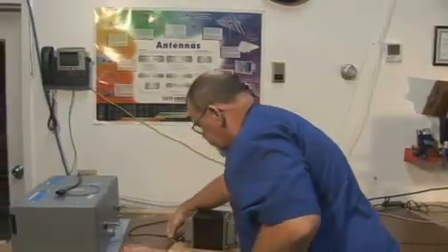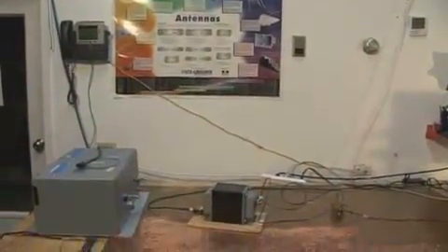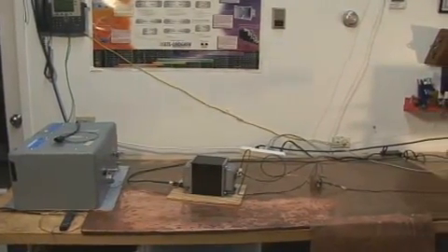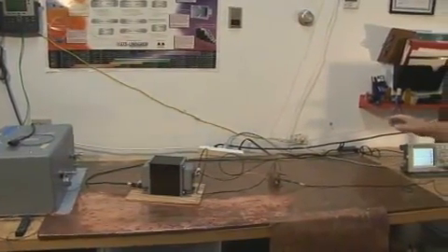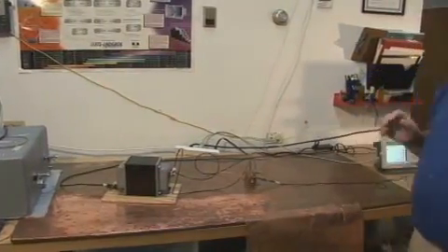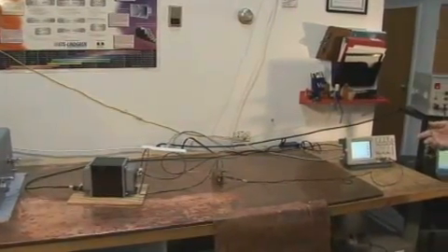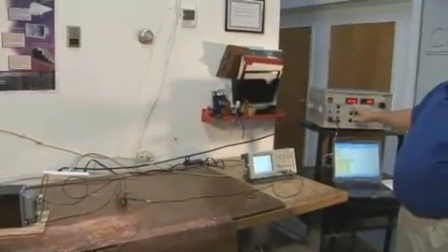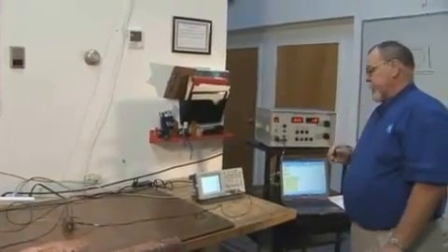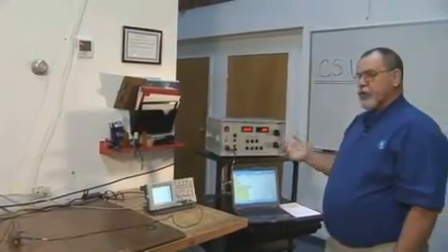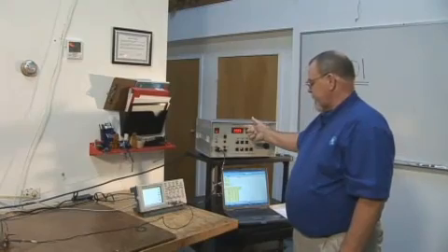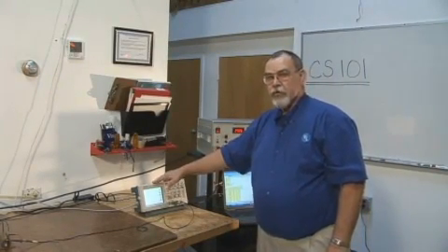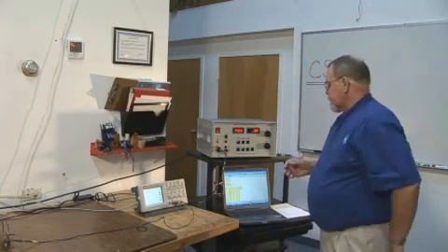And now I basically have all of the instrumentation that I'll be using during the test. The power amplifier, the signal generator, the oscilloscope for measuring, and the transformer. Note that I did not point out a voltmeter for measuring the output. That is built into the instrument. So we have a voltmeter built onto the item. So we'll be monitoring all of those items, recording what the voltmeter setting was when we got the power dissipation that we said we were going to. With that, let me get started.